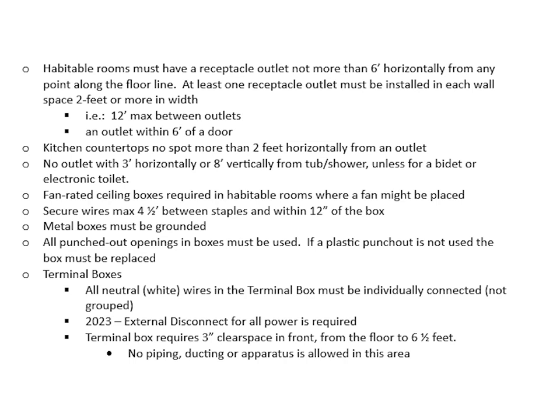Habitable rooms must have a receptacle outlet not more than 6 feet horizontally from any point along the floor line. At least 1 receptacle outlet must be installed in each wall space 2 feet or more in width. This means 12-foot maximum between outlets and an outlet within 6 feet of a door. Kitchen countertops, no spot more than 2 feet horizontally from an outlet. No outlet within 3 feet horizontally or 8 feet vertically from a tub or shower, unless for a bidet or electronic toilet. Fan-rated ceiling boxes are required in habitable rooms where a fan might be placed.